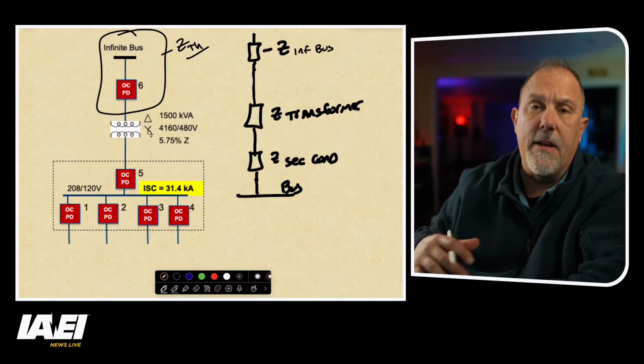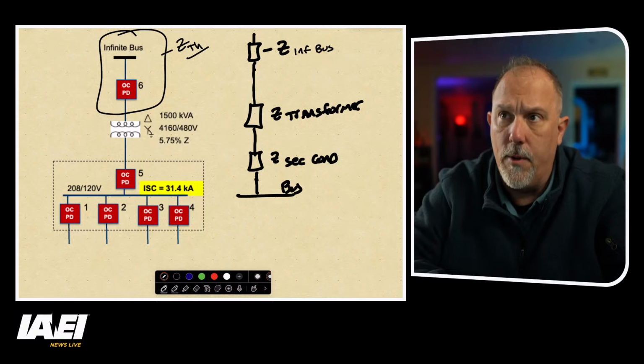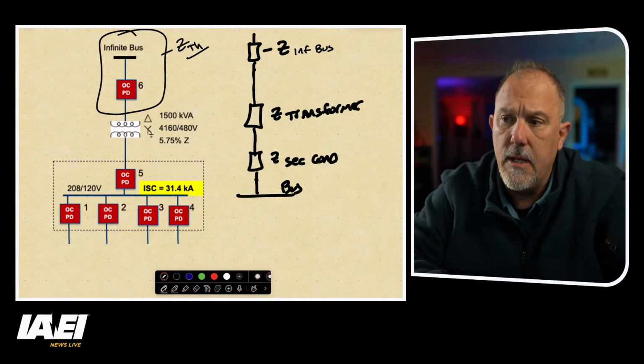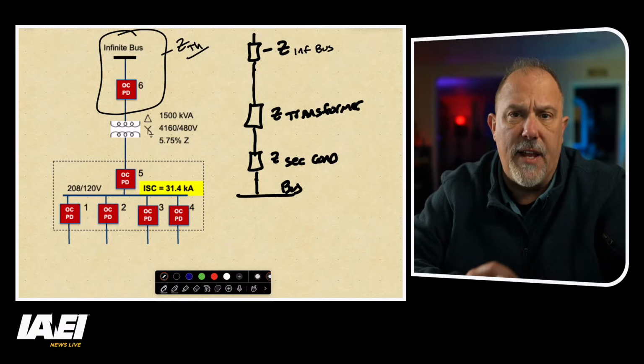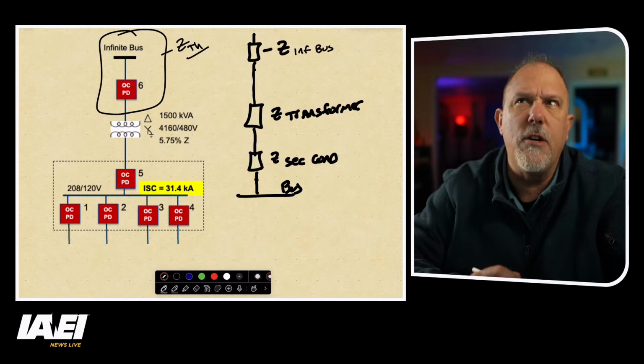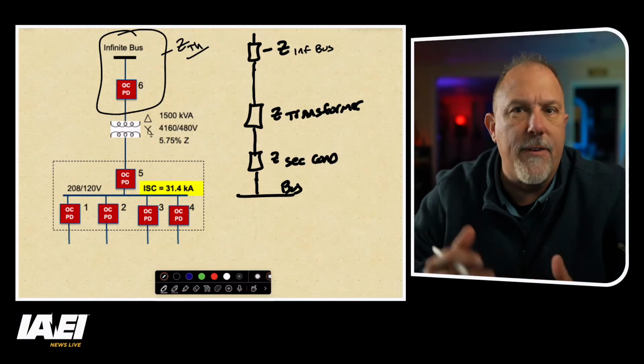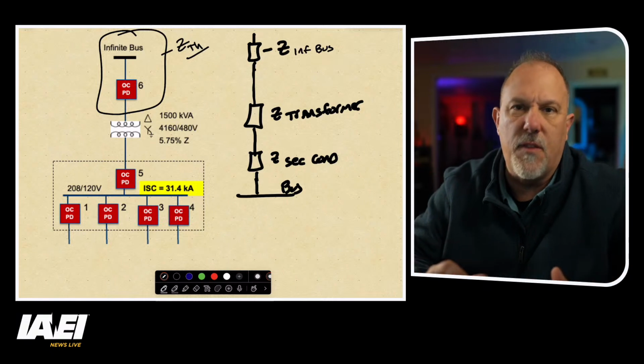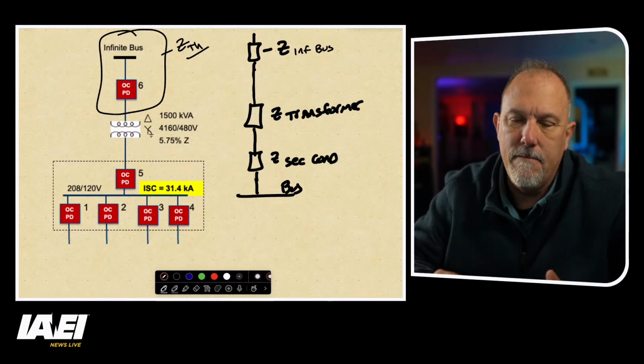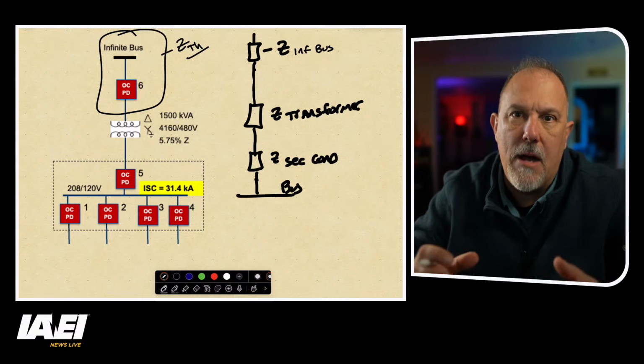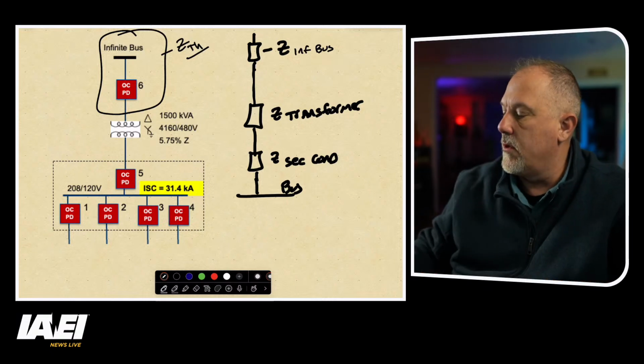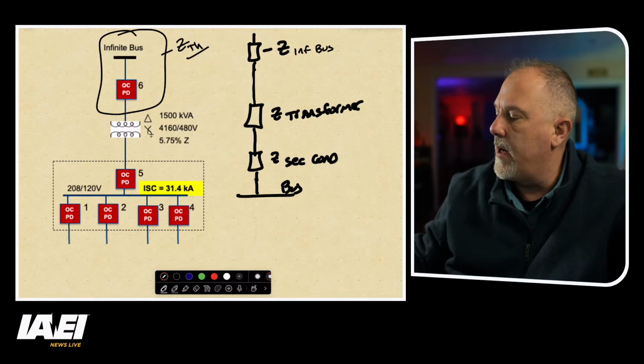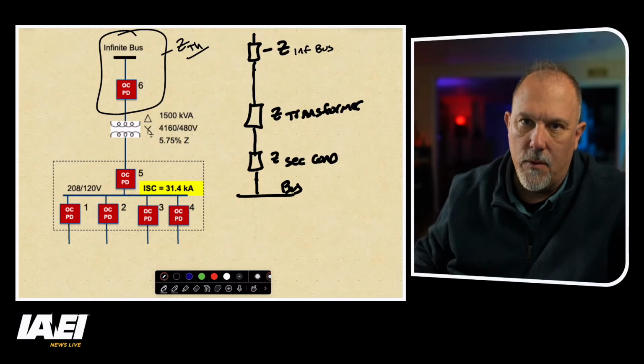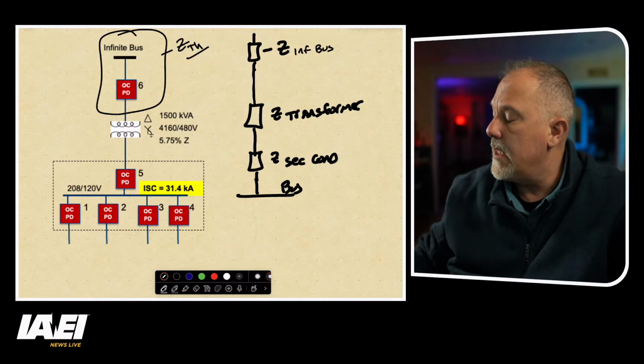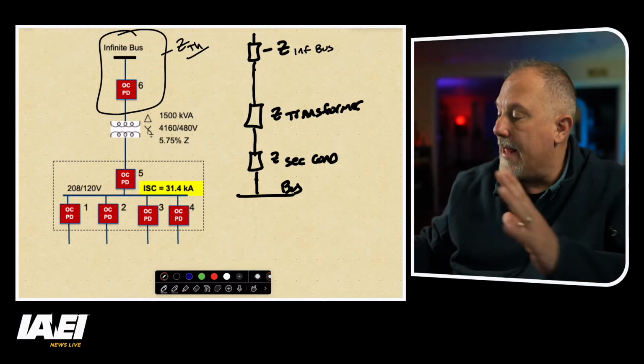But when we say an infinite bus, what we mean is an infinite amount of available fault current at that point in the system. Quadrillion, billion, gadillions, whatever you want to call it. It's the biggest number you can think of for fault current. An infinite amount of fault current at the source. So I'm not worried about the conductor on the primary of that transformer is my point. But that's basically what we're doing.